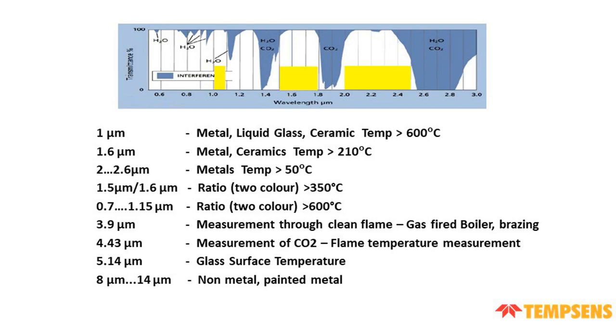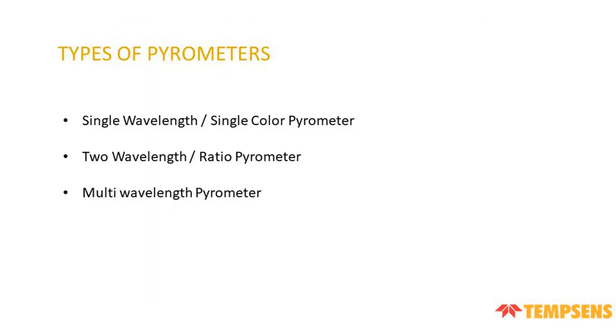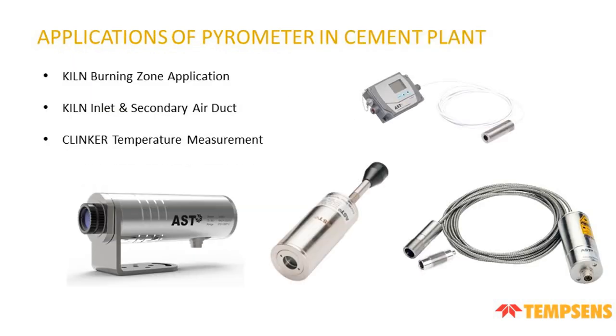3.9 micrometer: measurement through clean flame, gas fired and brazing application. 4.14, 4.43: measurement for coke CO2 flame temperature measurement. 5.14 for glass surface temperature measurement. 8 micrometer to 14 micrometer: non-metal and painted metal surface. Types of pyrometer: single wavelength or single color pyrometer, two wavelength ratio pyrometer, multi-wavelength pyrometer.